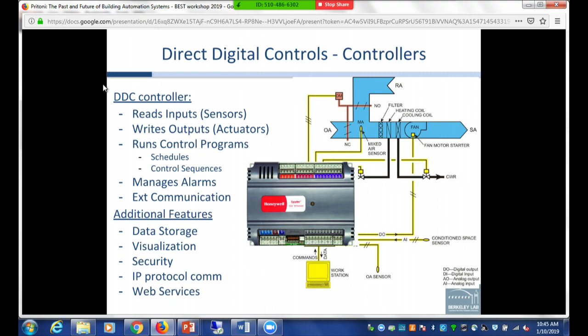You can have control code running on this thing. You can have schedules, and control sequences that say, if the outdoor temperature is lower than some value, considering enthalpy and so on, then change the speed of the fan. That was a very quick explanation of a control sequence. You also have alarms you can manage, and external communication.